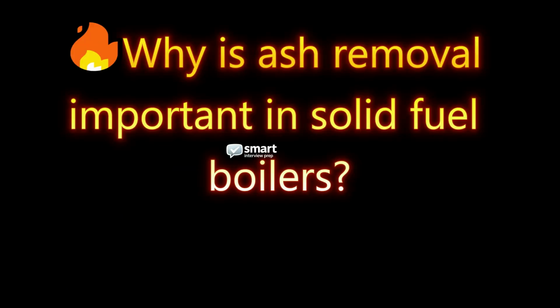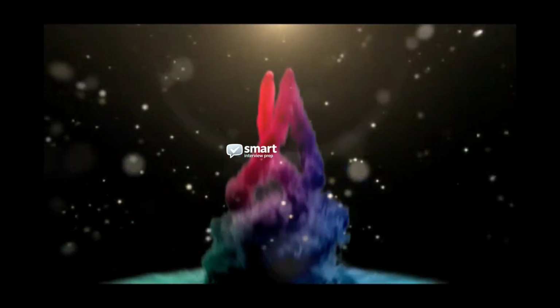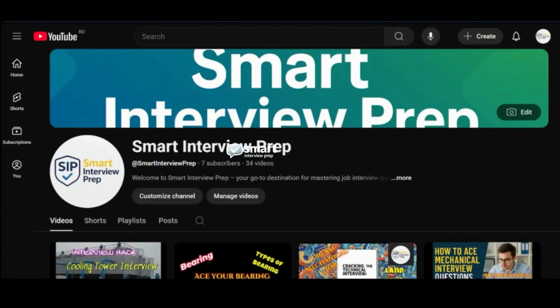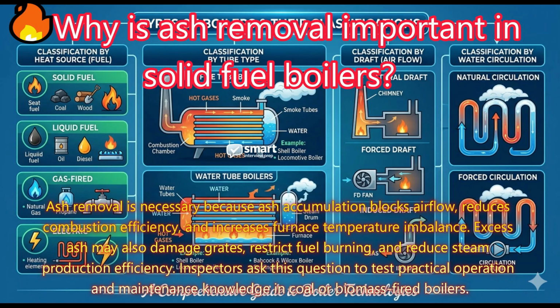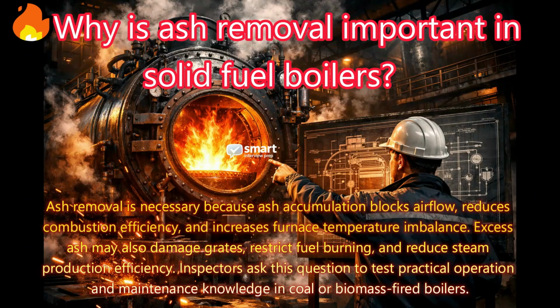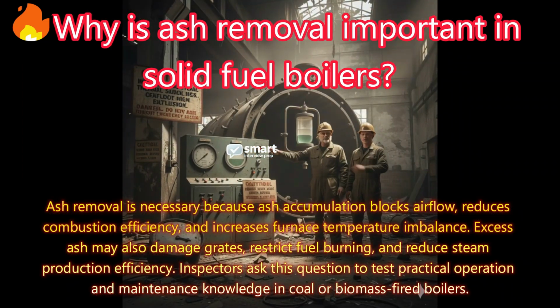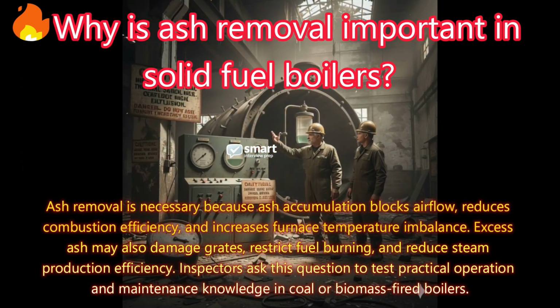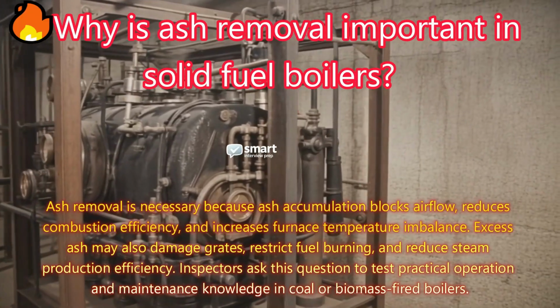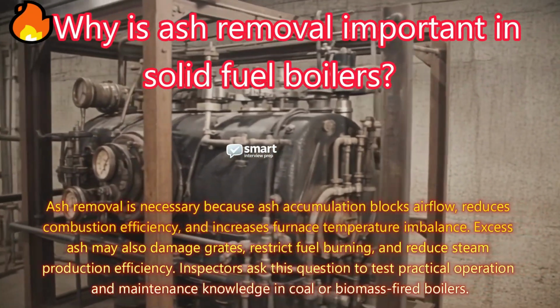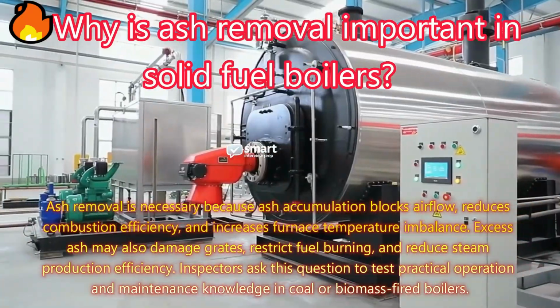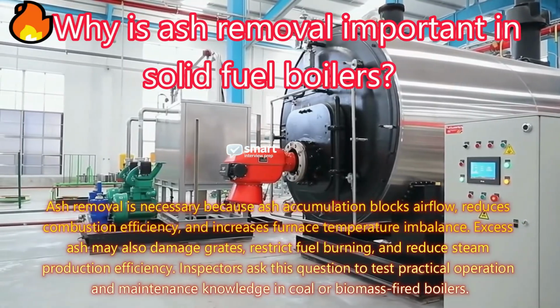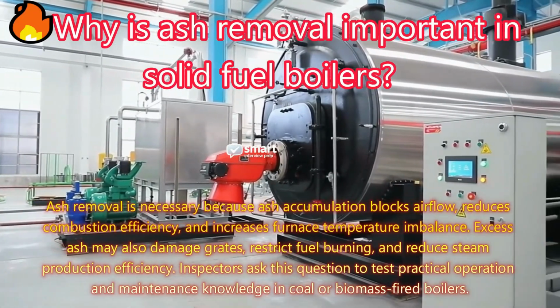Why is ash removal important in solid fuel boilers? Answer. Ash removal is necessary because ash accumulation blocks airflow, reduces combustion efficiency, and increases furnace temperature imbalance. Excess ash may also damage grates, restrict fuel burning, and reduce steam production efficiency. Inspectors ask this question to test practical operation and maintenance knowledge in coal or biomass-fired boilers.